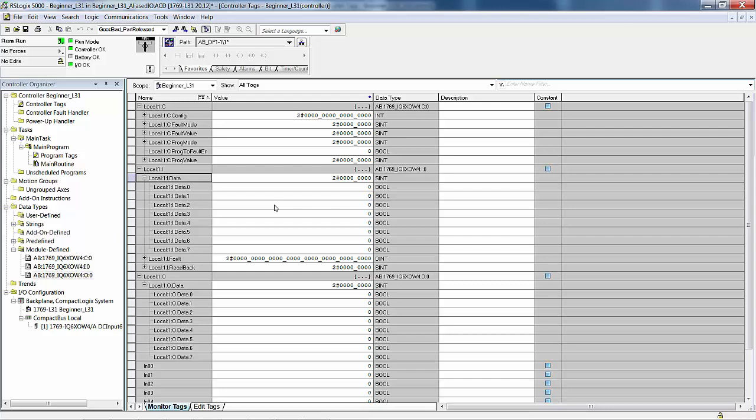the state changes from 0 to 1. The corresponding output relay contact closes if the processor is in the run mode. Now that is true. We're going to cover this in our lab, but as long as we're right here, I'm going to show it to you. You're going to see it again when you do the lab. So we're looking at the inputs here, and we see the inputs update whether you're in the program mode or the run mode. The outputs, however, whatever the state of this bit, it won't actually go out to that output device unless you're in the run mode.